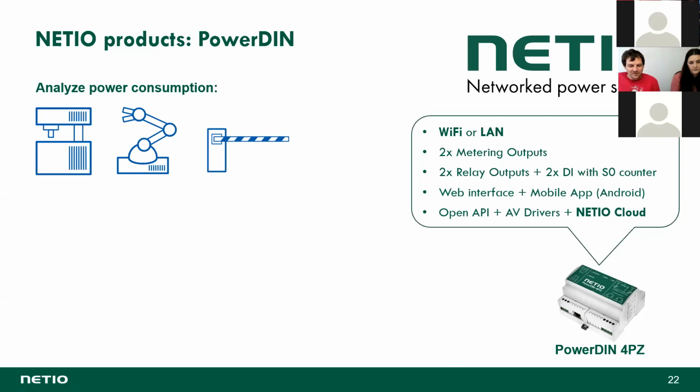Of course, a lot of people, when we are talking about this application to monitor if the gate is open or closed, they are saying, yeah, but dry contact in the end is easy. I say, yes, it is. But how much will the installation of that cost you? 200 euros, 250 euros, 300 euros? And it's unpredictable. But the installation of the power metering, it's a fixed cost. And you exactly know how much it will cost. So in the end of the day, if you have 500 parking lots and you want to monitor 500 of those, it's much cheaper to monitor that from the power than to install their special new sensor.